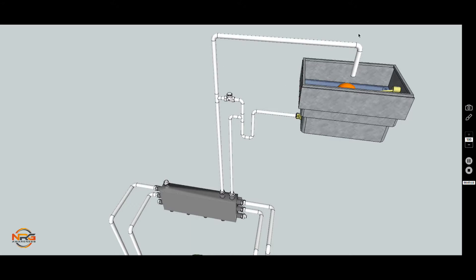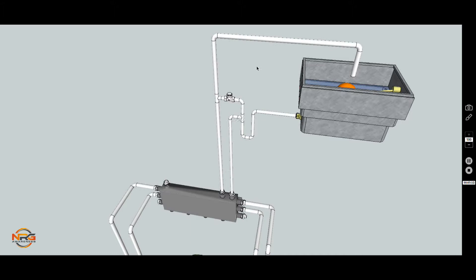But if there was ever a danger that pumping over might be a problem because you can't get your expansion high enough, then it's an idea to consider putting in a T and a non-return valve. If water is ever rising up this pipe, it would put pressure on the gate of the non-return valve. The water would go through the valve and down and back to where it came from and not rise up the expansion. The hottest water here will be trapped above the heat lock loop, which should be as deep as possible. The further you go down with this loop, the better, to make sure there's no chance of heat rising whatsoever into that tank. So the expansion and cold feed pipe will work away perfectly unhindered, and there's cold water available always to top up the system.